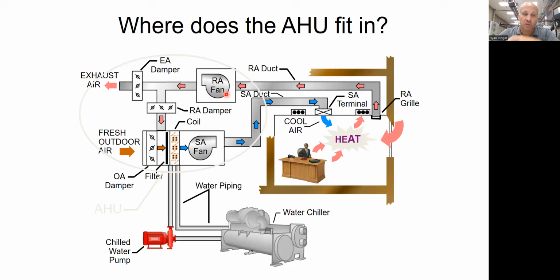There could be a separate external return fan, this damper over here at the exterior wall, or all of it can be in one box. Either way, we'd call it the air handling system, whether it's in one box or distributed boxes for space reasons. It sucks return air back. Some of that air gets brought back to the supply side of the air handler and mixes with outside air. So we mix outside fresh air and return air together.